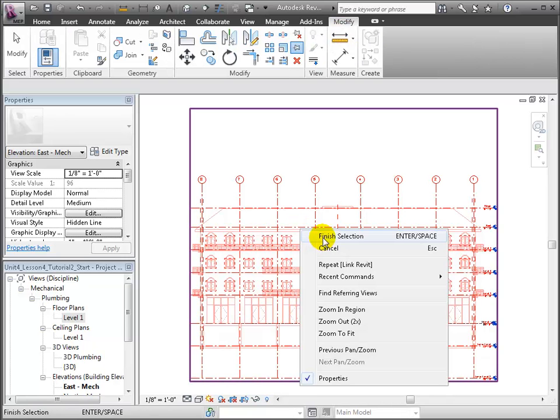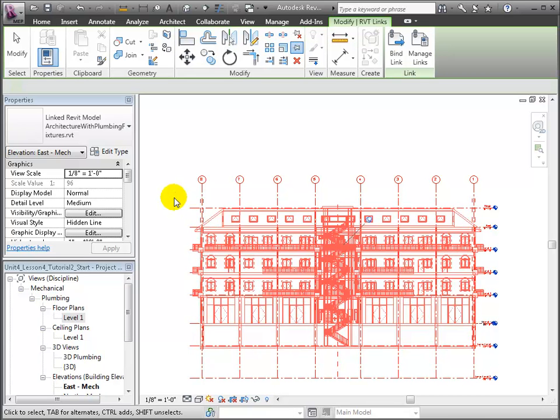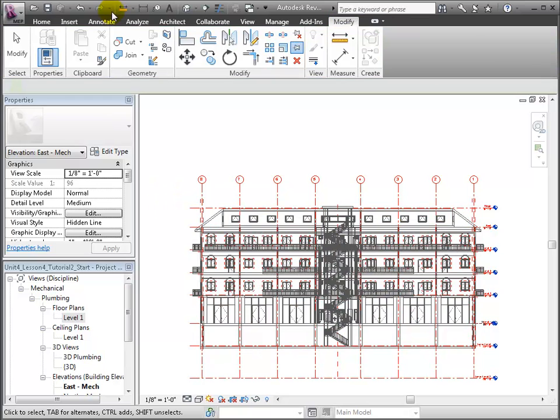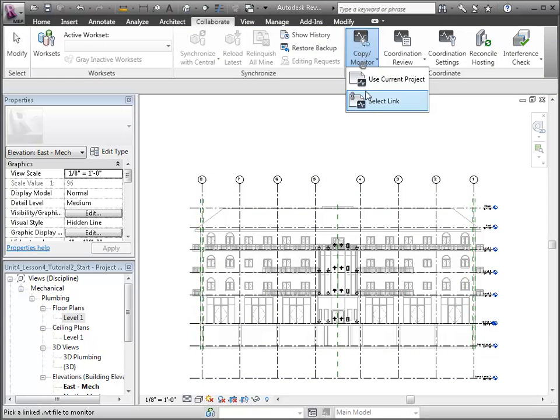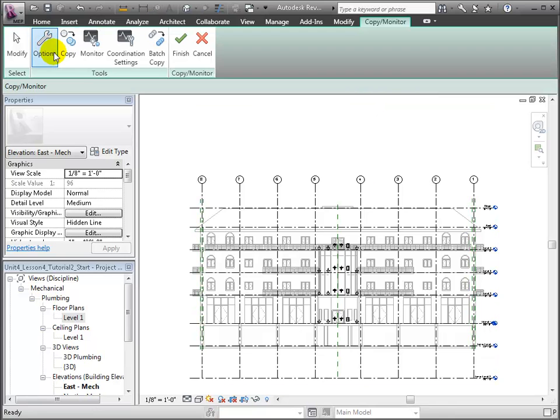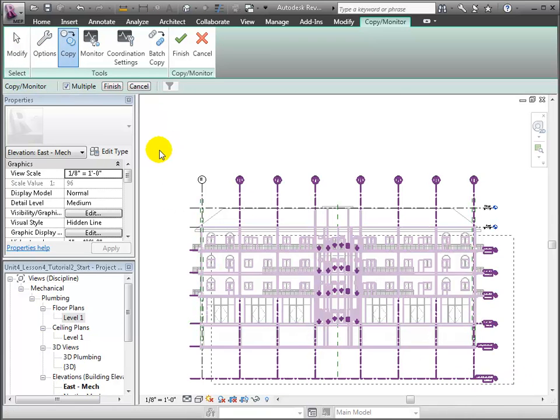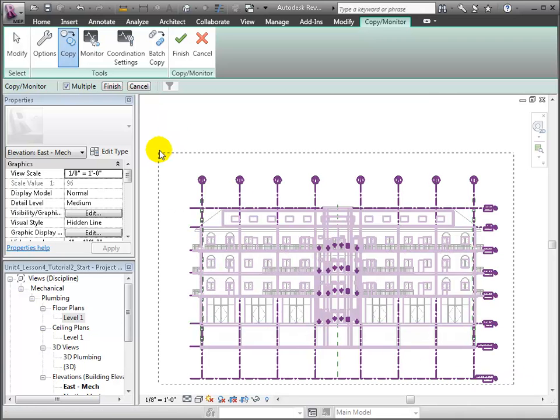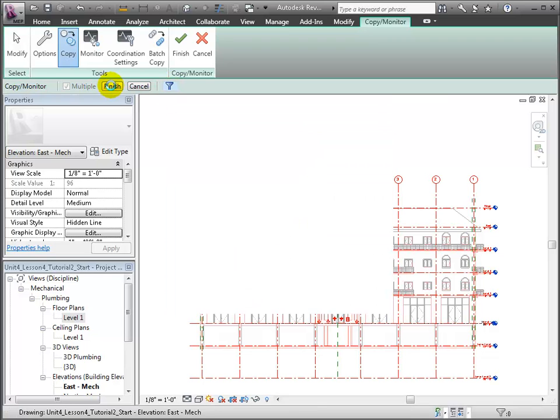Next we'll copy the shared levels and grids into our host project to help us get started. Use the Copy Monitor tool in the Collaborate tab and select the linked model. Then we'll click the Copy tool and turn on the Multiple option to copy in several items at once. Use a drag selection to copy all the available elements and we'll filter out the selection to include only grids and levels. Click OK to close the filter dialog and click Finish in the Options bar to complete our selection in this view.